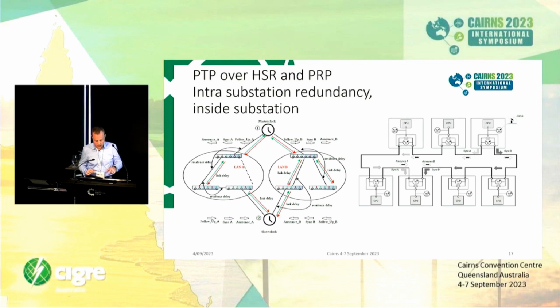Here are two pictures. On the left-hand side we have LAN A and LAN B. This is PRP, where my master clock sends the timing message to both LAN A and LAN B, and the LANs work as a normal PRP LAN. The slave clock then receives the same time from both directions. This is not the same as having boundary clocks where I receive timing from two devices and use the BMC algorithm to detect which one is best. This is a more primitive way to do it.